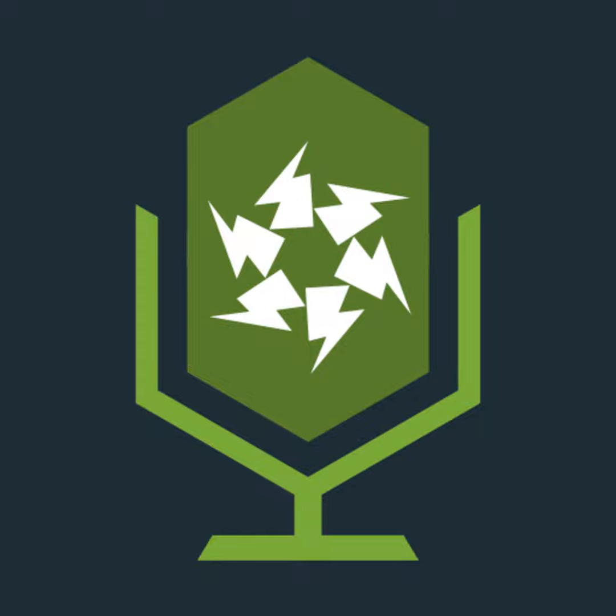Now with the TNS, it goes to neutral, but then it's a separate protective conductor in Earth. So a separate Earth is run. And so you can see there's an L1, L2, L3, neutral and protective conductor line. If you look at the TNCS though, with the PME, it actually stays as a combined conductor. And so it's only a line 1, line 2, line 3, and a combined conductor known as a PEN. And then the separation occurs at the client's end. So if you don't understand the difference between those two drawings, do study them a bit more.